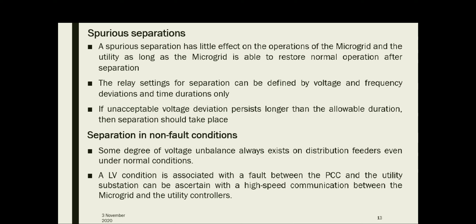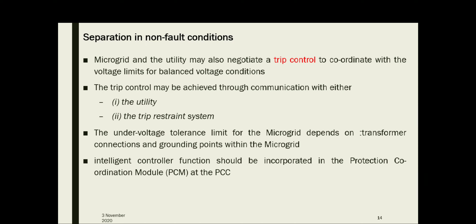Trip control may be achieved through communication with either the utility or a trip-restraint system. Some degree of voltage unbalance always exists on distribution feeders even under normal conditions. The voltage tolerance limit for the microgrid depends upon factors like transformer connections and grounding points within the microgrid. Therefore, an intelligent controller function should be incorporated in the protection coordination module at PCC to make the appropriate decision of whether to separate or not, based upon voltage unbalance.